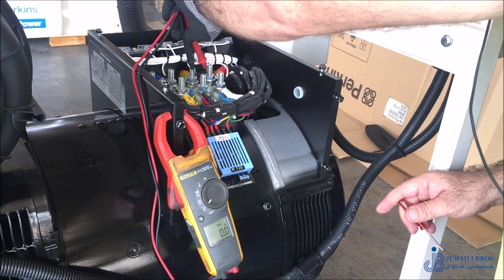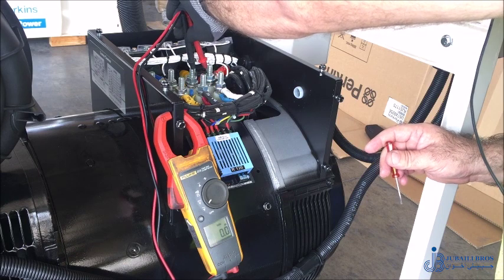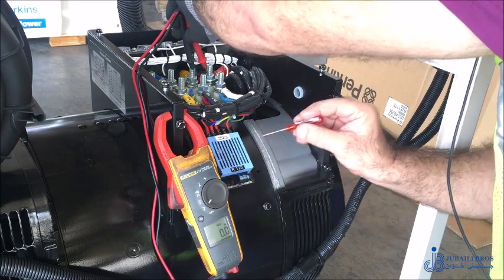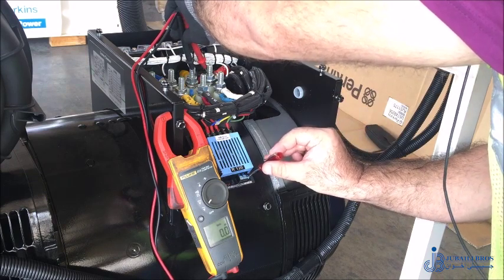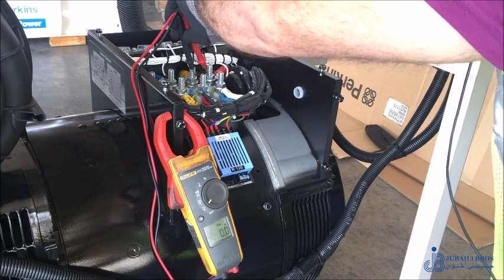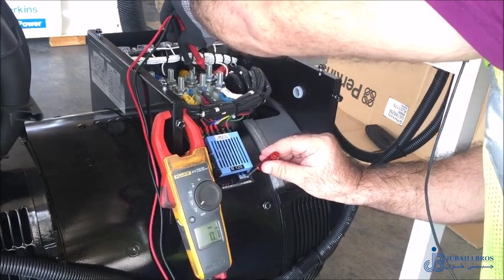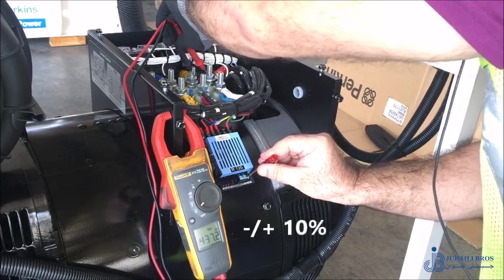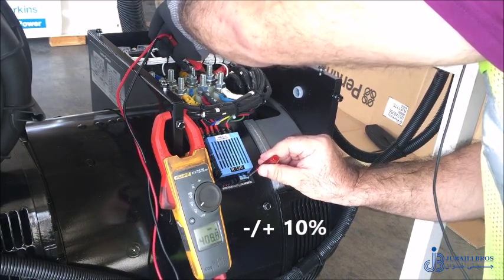Put the multimeter terminals on two of the phases. If you want to adjust the higher voltage for 400 volts, keep the multimeter on AC voltage. At the same time, be ready to use the voltage trimmer, which is a potentiometer inside, capable of increasing and decreasing by plus or minus 10 percent. By this we can increase and decrease the voltage up to the limit we need.